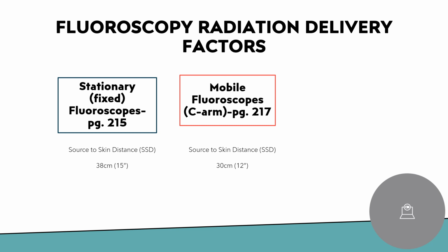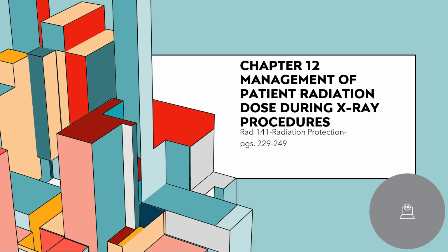As I stated earlier, your stationary fixed fluoroscopes are on page 215, and the source to skin distance should not be closer than 38 centimeters or 15 inches. And for mobile fluoroscopy or C-arm, which is on page 217, the source to skin distance should not be less than 30 centimeters or 12 inches. We're now going to move on to chapter 12, which is management of patient radiation dose during X-ray procedures. That begins on page 229 of your book.